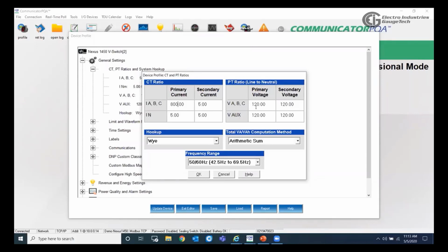Then we have the PT ratio, and the same idea. We would set the PT ratio based on the PT size we are using. But if we are not using any PTs there, it's very important also to set the PT ratio correctly based on the system voltage. So for example, if we are using the meter at a 208, 120 system, we will set the ratio to be 120, 120. We are using the line to neutral voltage. But if it's at 480, 277, I will set this to 277 and the secondary also 277. So the ratio would still be 1, like if we do it like this, or 120, 120.